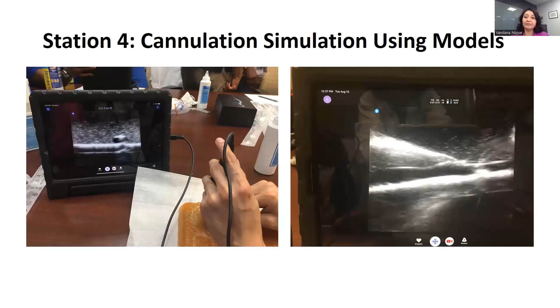Next slide, please. And on the fifth station, we discussed how they were going to assess an access for maturity for cannulation. And we discussed the rule of sixes, which means that you should have a diameter that's at least 6 millimeters. It should be less than 6 millimeters from the surface of the skin, and there should be a 6 centimeter straight segment. There is another component of the rule of sixes, a blood flow of 600 mils per minute, but our device was not capable of flow measurements. We did emphasize that ultrasound is an adjunct. It's not a replacement for physical examination and clinical experience. And all of these need to be used together to assess access maturity.